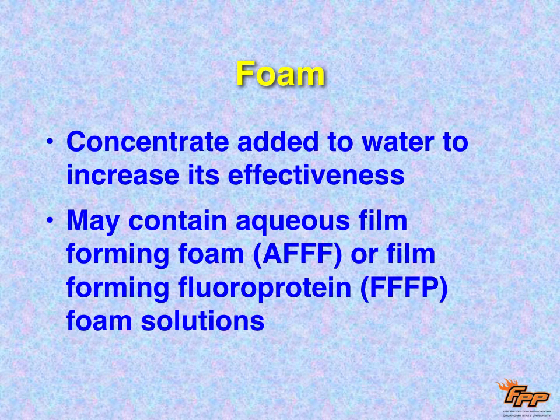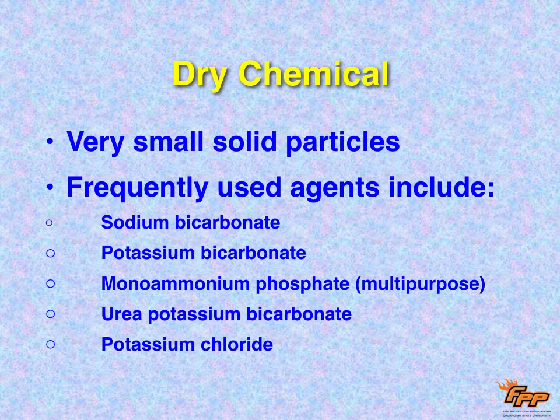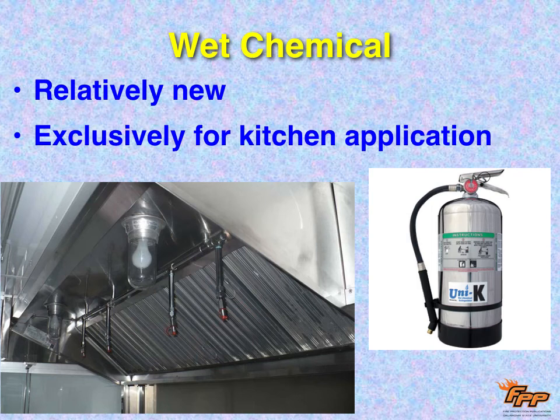Then we also have foam, which are different concentrates that are added to water. And we have the big systems, but we also have foam extinguishers. And then, of course, there's dry chem, which are little particles, little powders, and the frequently used agents are sodium bicarb, potassium bicarb, and all those others there. Wet chem is relatively new. It's been used in kitchens for fryers in professional kitchens because the newer oils that are used are really hard to put out. They run at very high temperatures, so wet chem will smother it and put it out. Dry chem won't necessarily put the fire out.